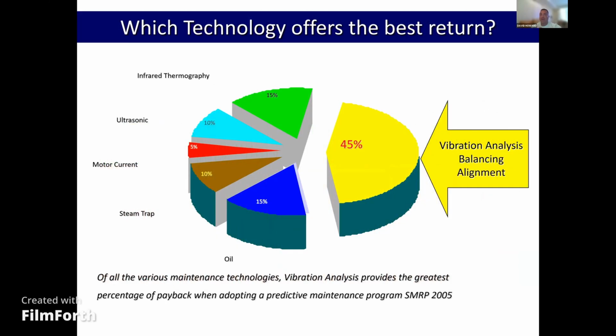So what we did at Airbus is we focused on the big three: vibration, balancing, and alignment represent 45% of predictive maintenance analysis and condition-based monitoring and online monitoring opportunities. If we look at all the failures and all the condition-based monitoring technologies out there, and go through a root cause failure analysis, a failure modes and effects analysis, we found that 45% of all the failures studied, over 1 million failures across numerous industries, vibration, balancing and alignment represented the root cause of 45% of those failures.